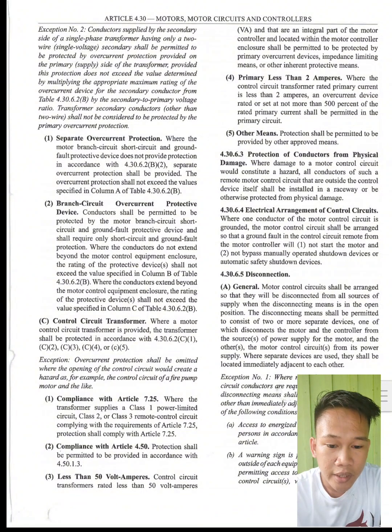Conductors supplied by the secondary side of a single phase transformer having only a 2-wire or single voltage secondary shall be permitted to be protected by the overcurrent protection provided on the primary side of the transformer, provided this protection does not exceed the value determined by multiplying the appropriate maximum rating of the overcurrent device for the secondary conductor from table 4.30.6.2b by the secondary to primary voltage ratio. Transformer secondary conductors other than 2-wire shall not be considered to be protected by the primary overcurrent protection.